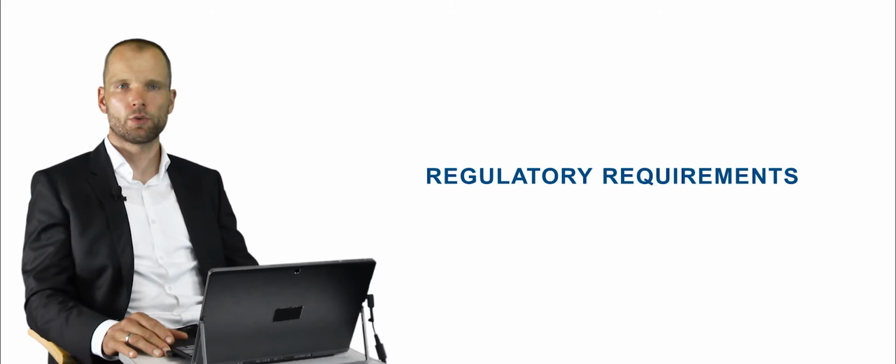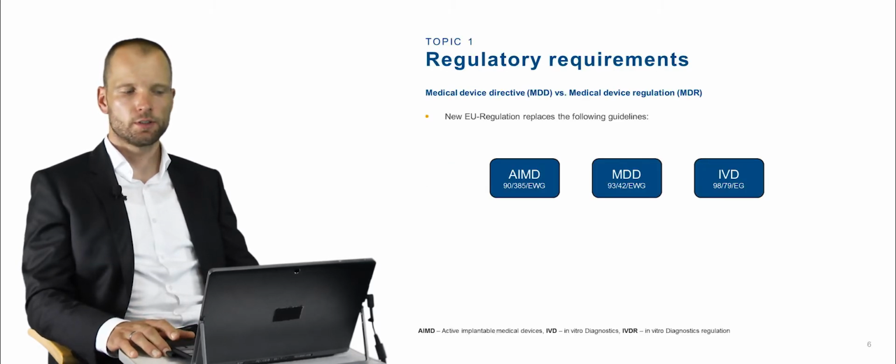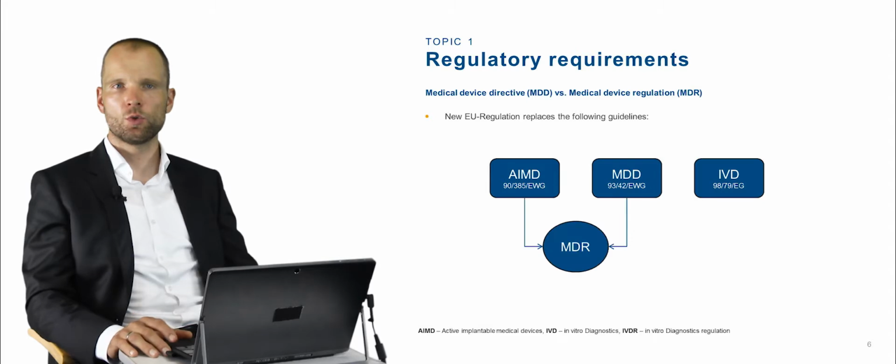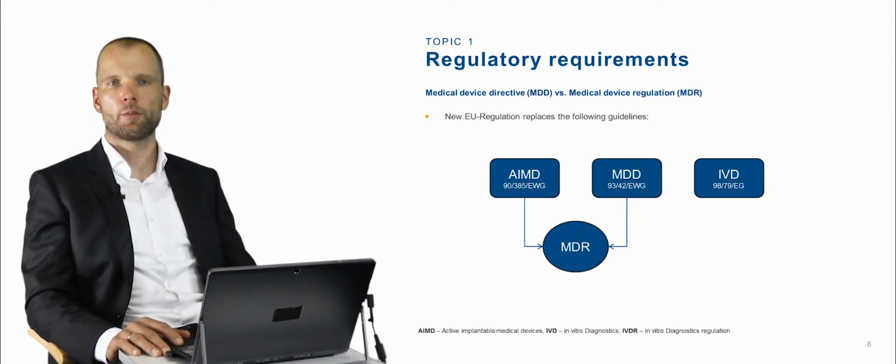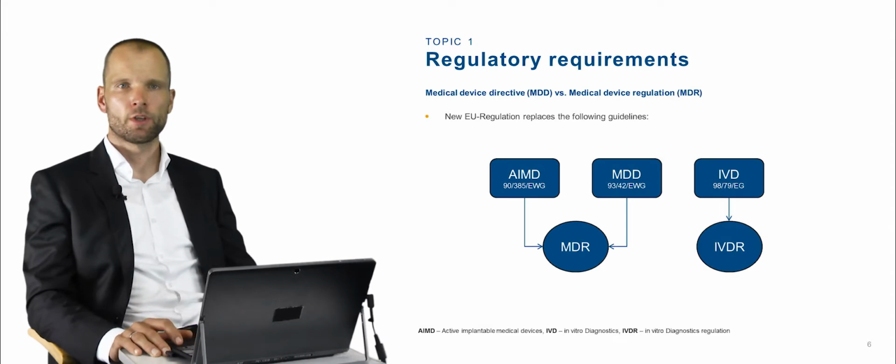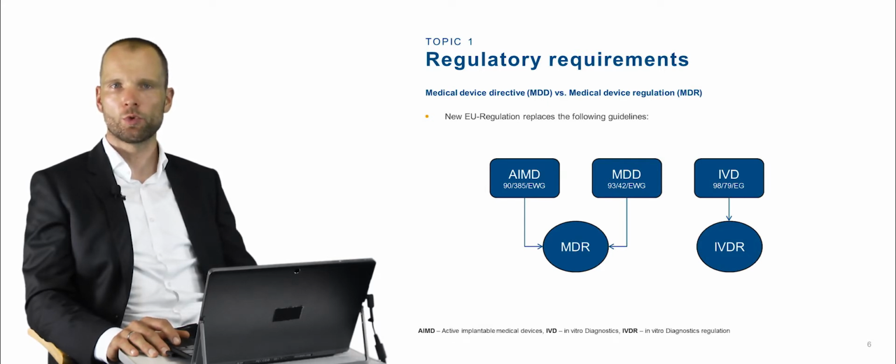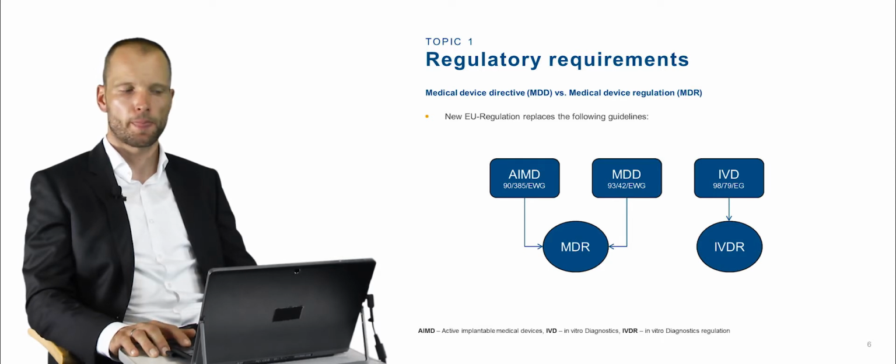Let's start with the regulatory requirements. Since 2017, we have the new medical device regulation. This regulation replaced the Active Implanted Medical Device Directive and the Medical Device Directive. We also have a new in vitro diagnostic regulation, which replaces the in vitro diagnostic directive. Currently, we are in a transition period. From the 26th of May 2020, all medical devices may only be approved by the medical device regulation.